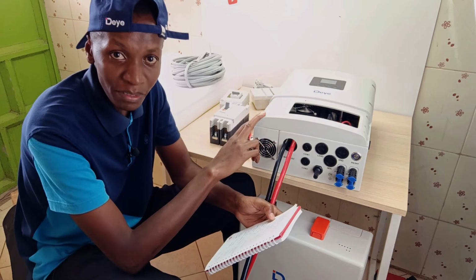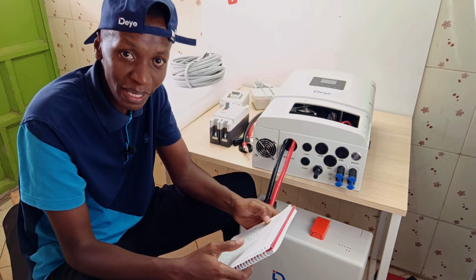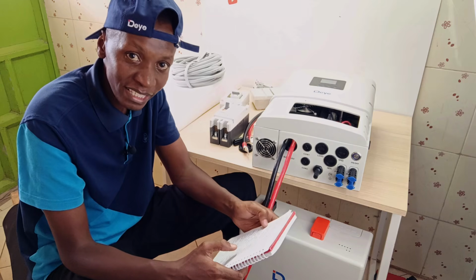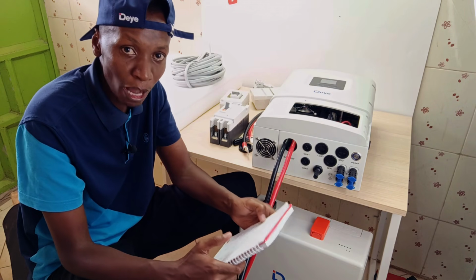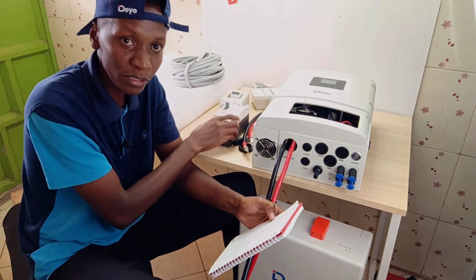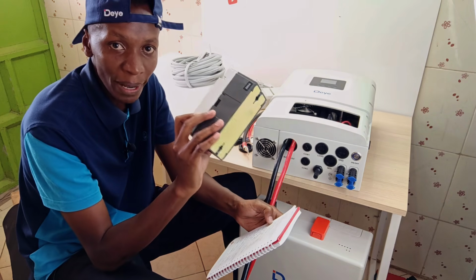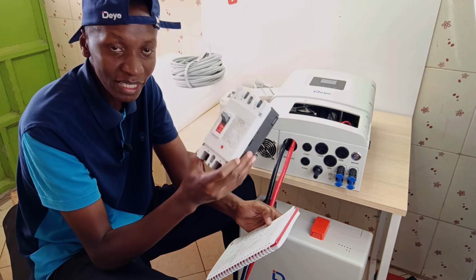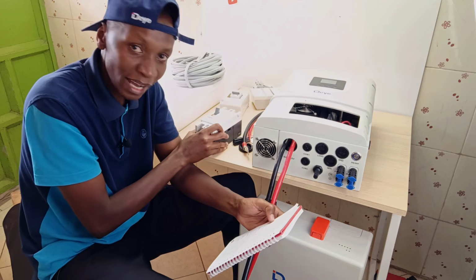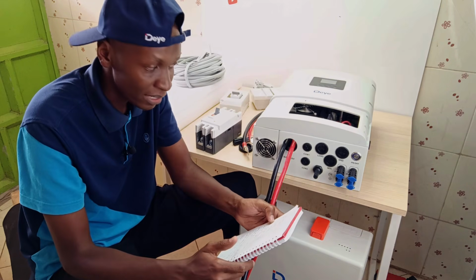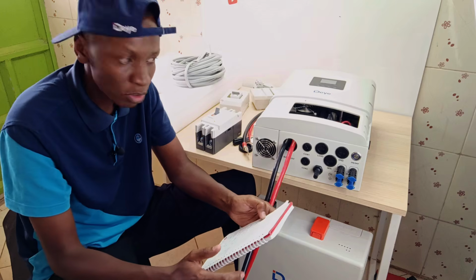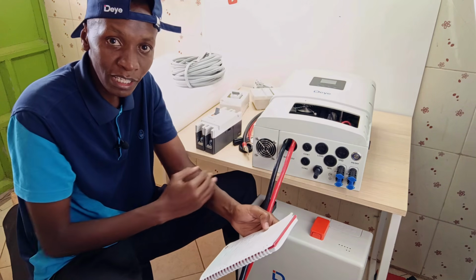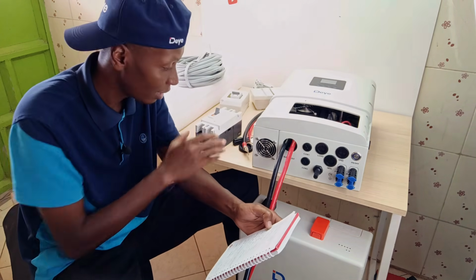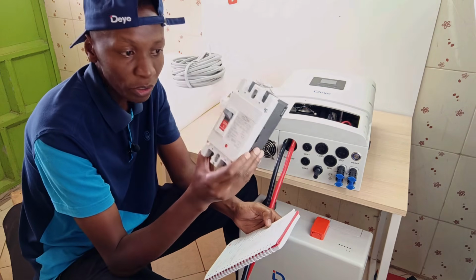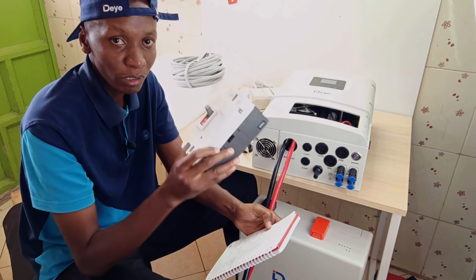The inverter has a maximum charging current of 135 amperes and also a maximum discharge current of 135 amperes. You can see it's very important because our breaker is way past that. It's a 200 amp DC breaker, but the maximum discharging current is 135 amperes. So whenever anything goes wrong between the inverter and the battery, if it crosses that 200 amp mark, this DC breaker is going to shut itself down automatically.